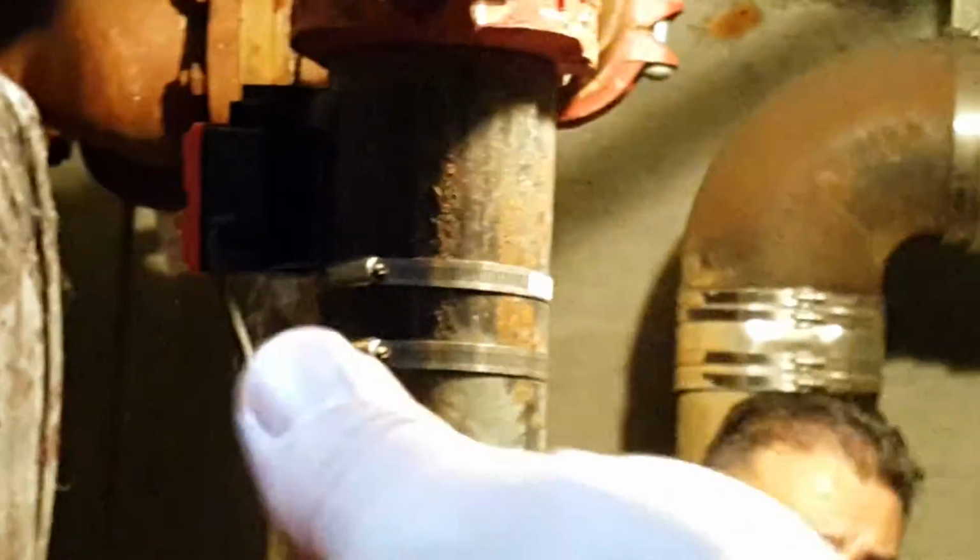And that's your discharge. The reason why you shut that valve is because this fire pump kicks on at a higher pressure and it's got more horsepower than the jockey pump. So you don't want to water hammer the system. You don't want it to surge up. You might break a fitting, you might pop a head. You don't want to cause any damage when you're just doing a test.